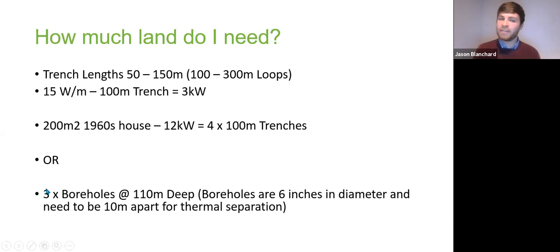Alternatively, there is vertical, which we'll explain a little bit more later on, but 3 boreholes at 110 meters deep. Boreholes, I know that the phrase borehole seems to scare a lot of people. They think of these huge gaping holes that are never ending. They're actually about 6 inches in diameter, and they need to be 10 meters apart for that thermal separation again.